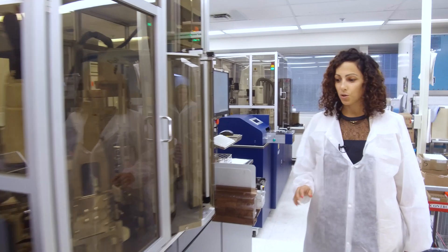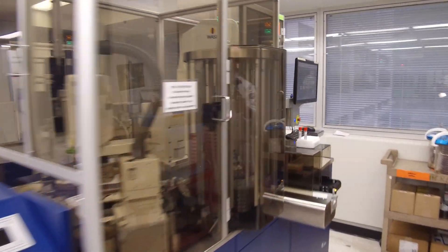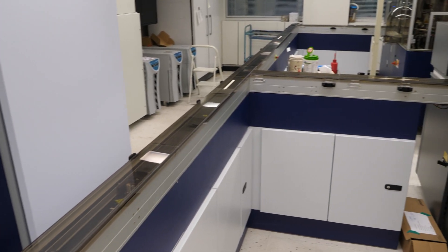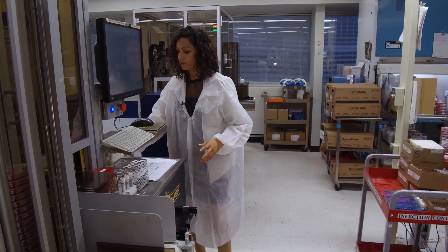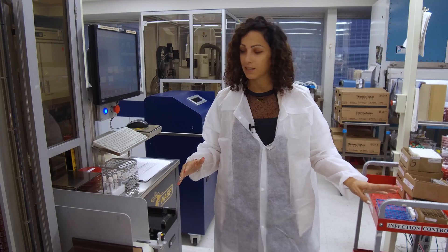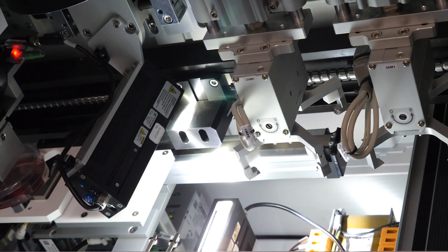What I want to show you here are the two WASPs installed at this hospital. This is an older WASP that is electrical and this is a WASP DT — both are considered electrical. They kept the older one, purchased a new one along with the WASP Lab, and attached the WASP Lab to both instruments. They used to receive every sample manually, which took a long time. Now these e-swabs go onto the WASP system — you hit start and it scans the barcode, receives the sample, saving staff time. It will plant, streak, send it on to the WASP Lab, perform a Gram stain if required, and a broth inoculation.